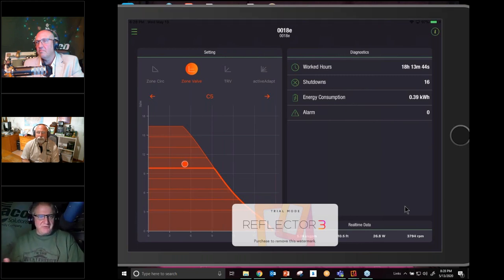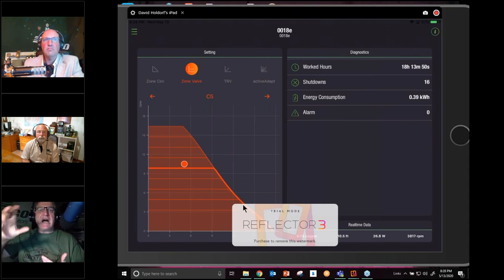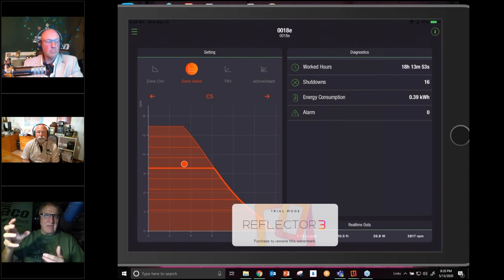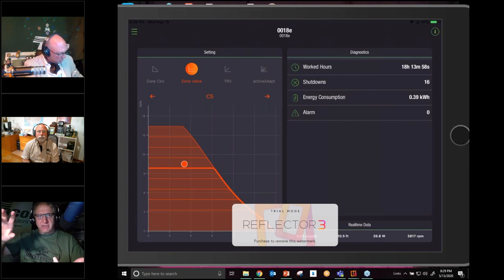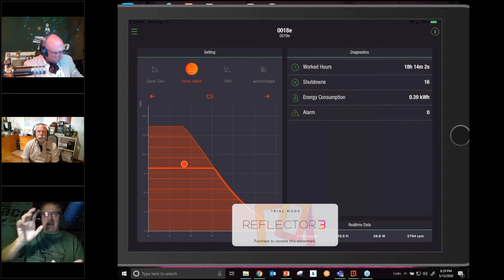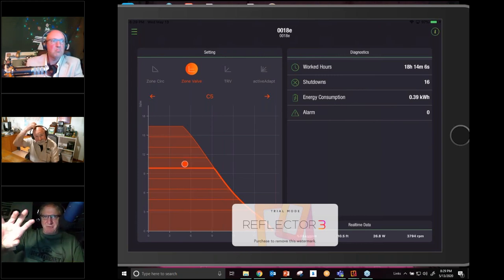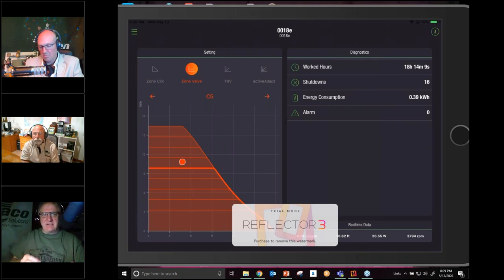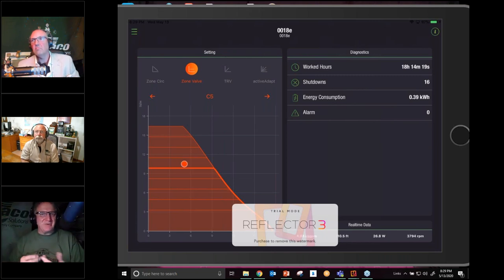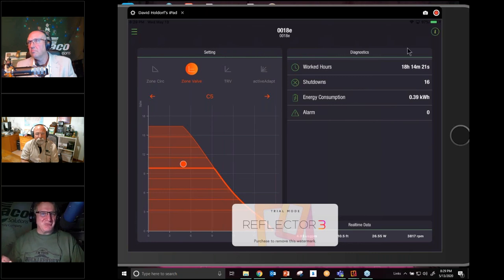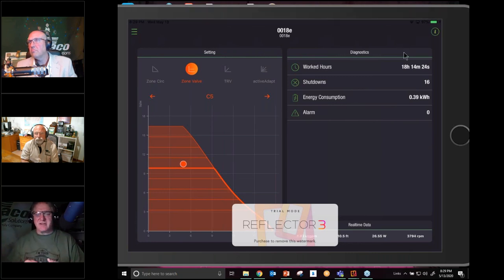That's part one. Part two of the failsafe is what we call sure start. If the rotor were to ever become locked up for whatever reason, the circulator knows it's supposed to be going. So what happens is we go into sure start mode. The control will rock that impeller back and forth very aggressively, 44 watts that way, 44 watts that way, to try to break it free. And it'll do this up to 100 cycles over a 20-minute time frame to try to break itself free. And in the real world, out there in the wild, we've seen it break free, what, guys, about 2, 3, 4 cycles at the most before it breaks itself free.